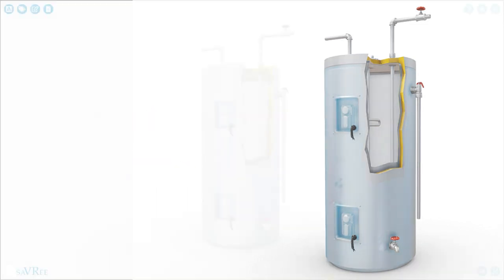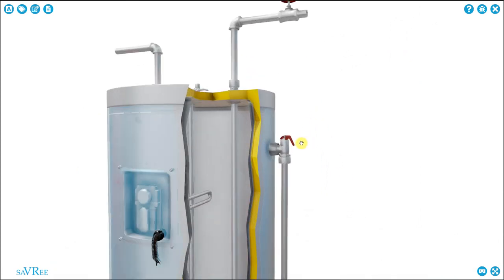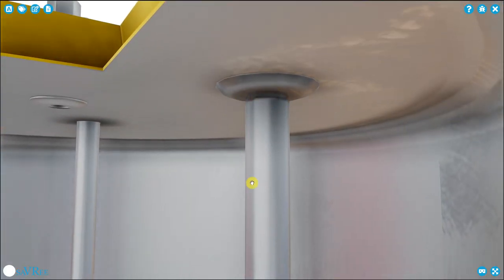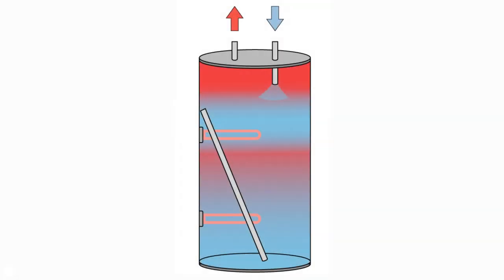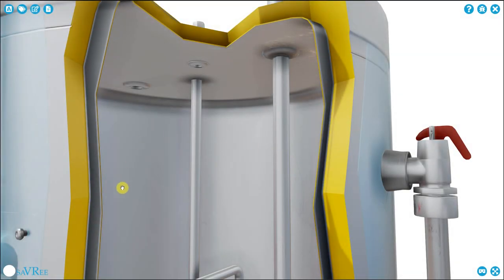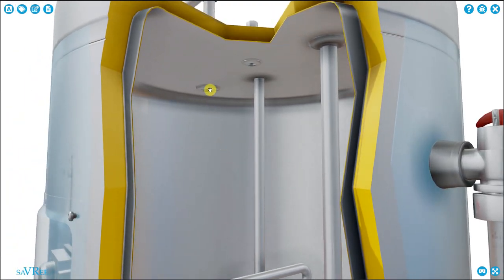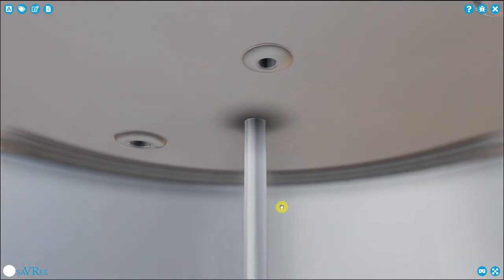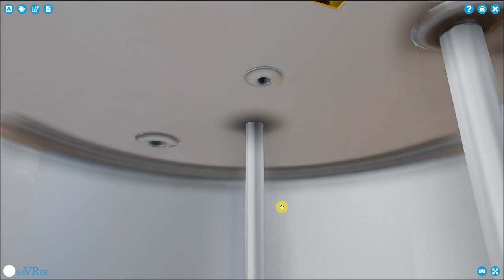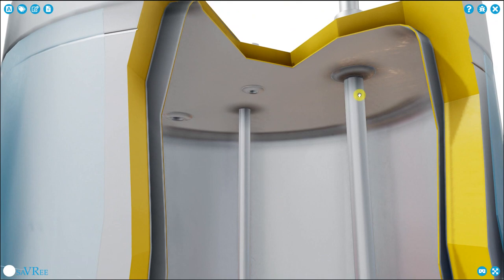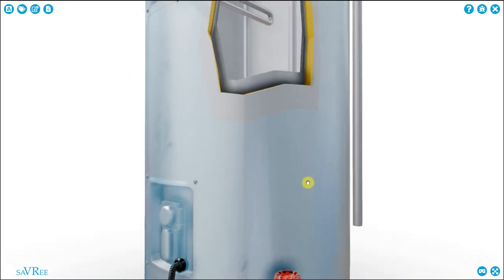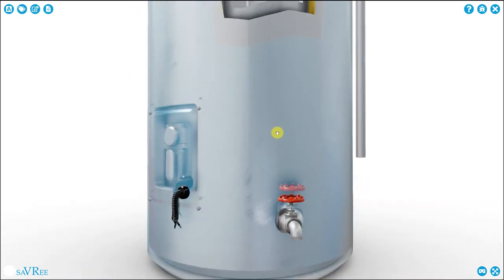So what are the problems that you're likely to encounter with your water heater? Well, one of the most common problems is that your dip tube breaks off from the top of the tank. It'll snap off about here and then fall to the base of the tank. We don't want this because that means the cold water is then discharged to the top of the tank. And if it's coming in and hanging around this section here at the top of the tank, then it's also going to be taken directly out of the top discharge here. Remember, this is our hot water outlet. So we're not going to get hot water at our tap, at our faucet, or in our shower. So the dip tube has to be there in order that the cold water goes to the base of the tank. To get around this problem, it is also possible to have your cold water inlet at the base of the water heater. It just depends upon the design you have.